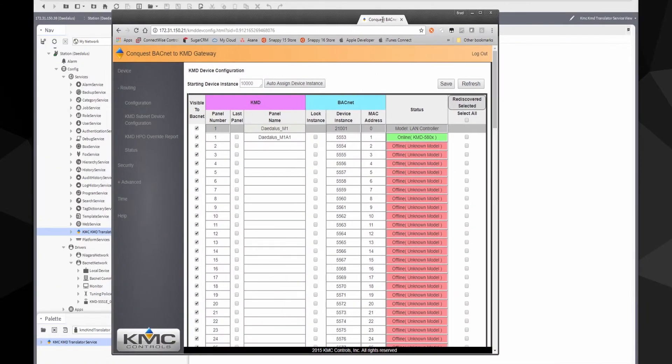One translator can handle one main panel and one subnet. For example, one LAN controller and two subnets would require two translators: one for the LAN controller and subnet A, and one translator for subnet B.